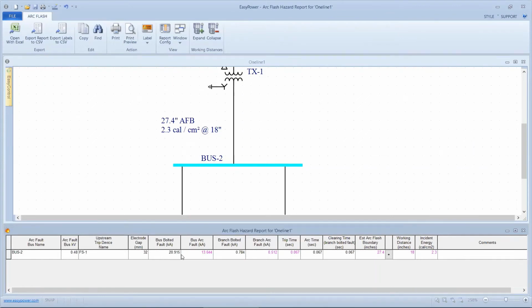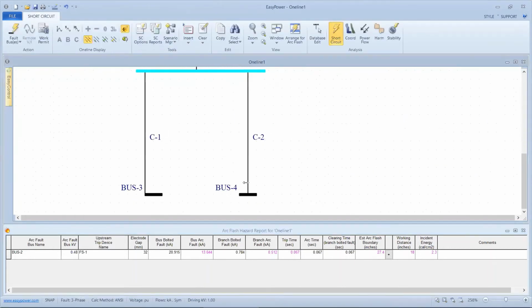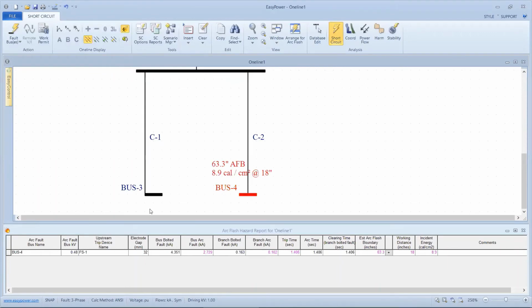We knew the bolted fault current. The arcing fault current is 13.664 kiloamps. According to the data sheet for that fuse, it'll take it 67 milliseconds to clear the arc. And that gives us the incident energy of 2.3 calories at a working distance of 18 inches. If we walk 1,000 feet away and have a fault on this bus, it's still 480 volts. It's still the same fuse. It's still the same air gap. But now the maximum current that an arc will draw is 2,729 amps. That means it will take almost 1.5 seconds for that fuse to clear the arc.